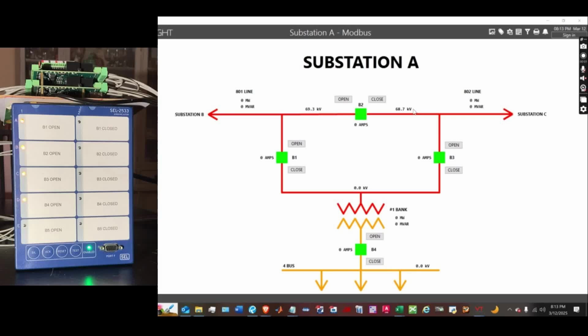Here we have the SEL 2533 breaker simulator on the left with the Raspberry Pi RTU sitting on top. And on the right hand side of the screen is the VTScada operator display. On the VTScada display, there's a 3-breaker ring bus with 2 incoming 69 kV lines and a 69 to 13.2 kV transformer. This is a pretty typical configuration for a small distribution substation.